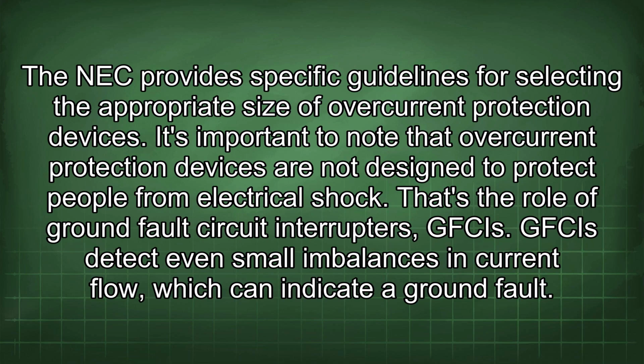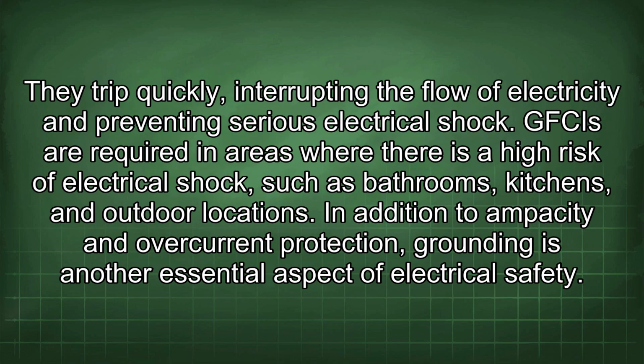The NEC provides specific guidelines for selecting the appropriate size of overcurrent protection devices. It's important to note that overcurrent protection devices are not designed to protect people from electrical shock. That's the role of ground fault circuit interrupters, GFCIs. GFCIs detect even small imbalances in current flow, which can indicate a ground fault. They trip quickly, interrupting the flow of electricity and preventing serious electrical shock. GFCIs are required in areas where there is a high risk of electrical shock, such as bathrooms, kitchens, and outdoor locations.